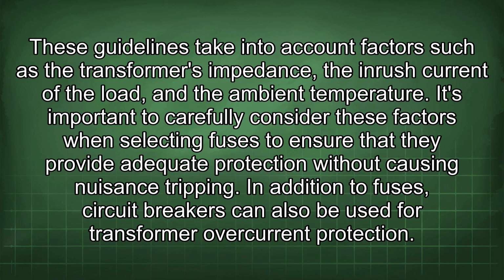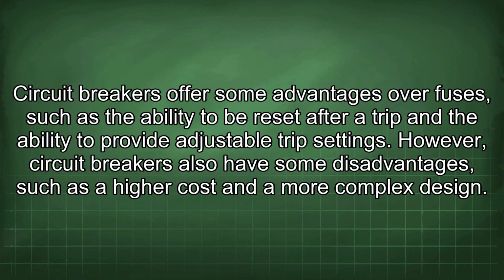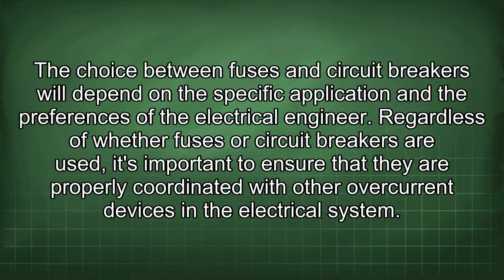In addition to fuses, circuit breakers can also be used for transformer overcurrent protection. Circuit breakers offer some advantages over fuses, such as the ability to be reset after a trip and the ability to provide adjustable trip settings. However, circuit breakers also have some disadvantages, such as a higher cost and a more complex design. The choice between fuses and circuit breakers will depend on the specific application and the preferences of the electrical engineer.